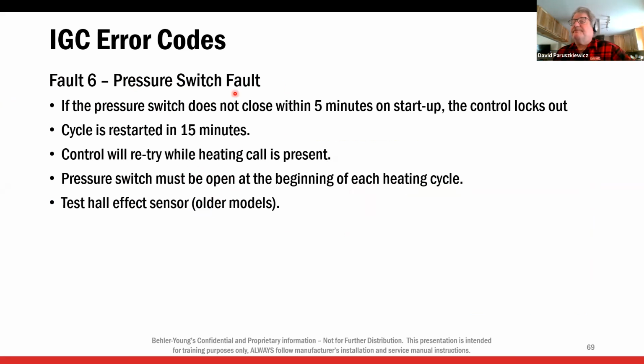Faulty pressure switch. That's pretty self-explanatory, but the pressure switch has to be open before it's closed. So if you are trying to jump out the pressure switch and then the inducer comes on, if the pressure switch is closed before the call, we're going to fault out. That's one of the things this fault means. So again, if I'm thinking the pressure switch is bad, I can just jump it out. Well, it won't work because if the switch is closed before the heating cycle starts, it'll trip, it'll lock out. All right. So if the pressure switch does not close within 5 minutes of the inducer coming on, we'll fault out.